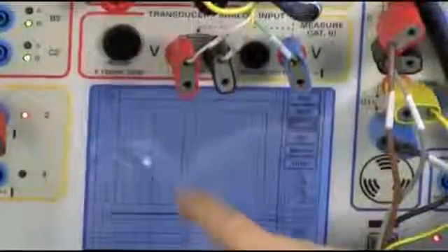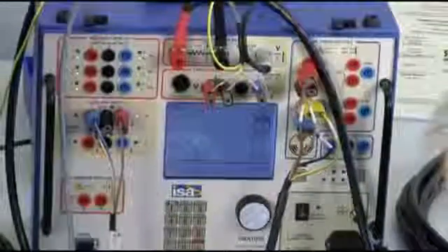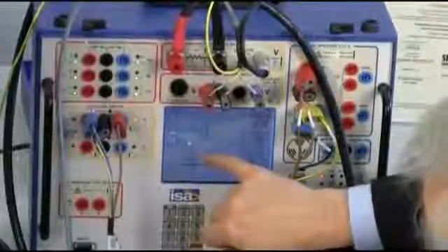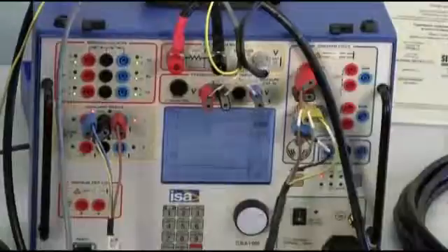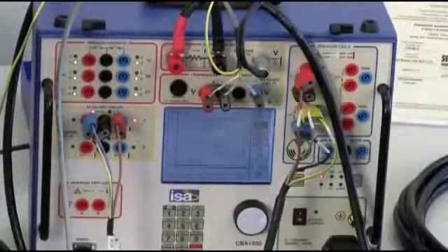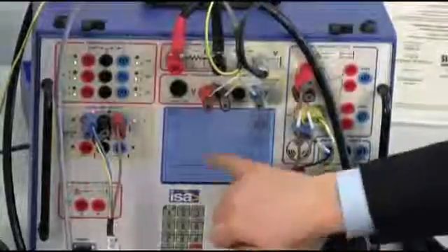What does it mean? It means that we have injected the current, the contact was closed, this is the value of the voltage drop across my closed contact, and this part here is the most important one, because that's the part when the contact actually moved and during which we have performed the recording.